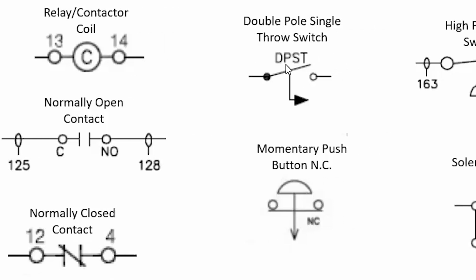This is a double pole single throw switch - this is just a toggle switch. I've been on systems where guys went through and forgot to check if the switch was on. Here's a momentary push button - I may have a pump skid where I have a temporary alarm, and I just want it there until you see it, then you push the button and it's off.